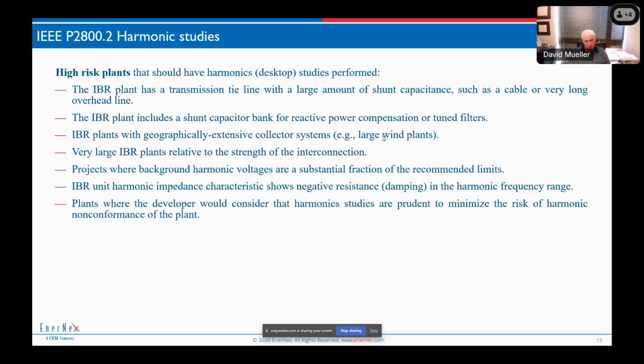If we have a shunt capacitor bank, that introduces a resonance phenomenon that we need to look at. If it's a very big collector system, really any large wind plant probably should have a harmonic study done. Very large IBR plants where we have a low short circuit ratio. We tried to define this, we tried to talk about the size of the plant, and we just could not come up with how to justify whatever short circuit ratio or size we put in there. So we left it kind of open.